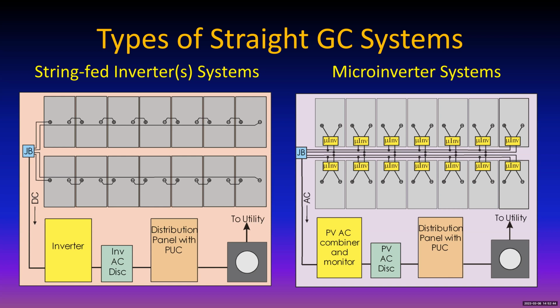It's current. So let's say the first one is putting out 1 amp, and the next one's doing 1.1 amps, and the next one's doing 0.5 amps, meaning the first 3 modules have different exposures to sunlight. Nobody cares because each one does what it can, and the current that comes out of the microinverters just adds up, and you get everything you can possibly get given the exposure conditions, without any one module messing up the performance of another module. So that's a major advantage of this system. Okay, and there's another similar system that we're going to look at as well.